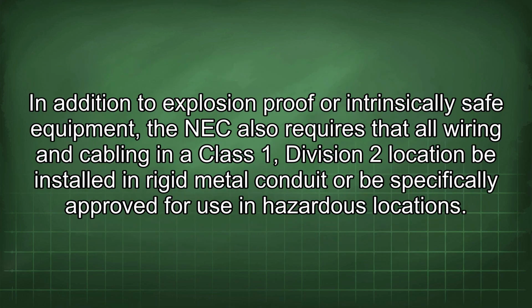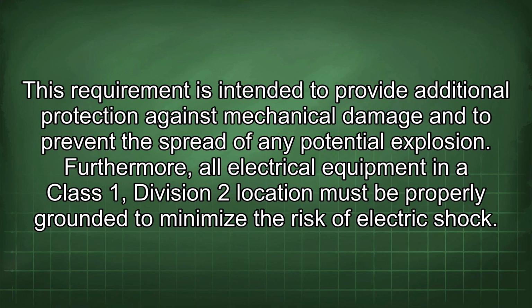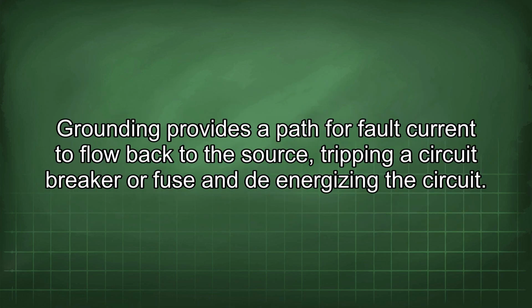In addition to explosion-proof or intrinsically safe equipment, the NEC also requires that all wiring and cabling in a Class 1, Division 2 location be installed in rigid metal conduit or be specifically approved for use in hazardous locations. This requirement is intended to provide additional protection against mechanical damage and to prevent the spread of any potential explosion. Furthermore, all electrical equipment in a Class 1, Division 2 location must be properly grounded to minimize the risk of electric shock. Grounding provides a path for fault current to flow back to the source, tripping a circuit breaker or fuse and de-energizing the circuit.